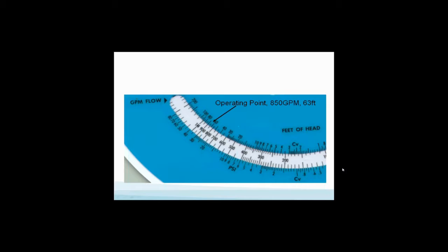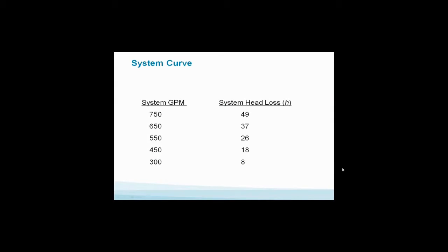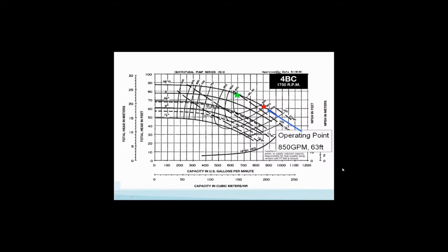And we pull these particular numbers off, any set of numbers you want to. In this case, we pull them off this way. 650 is 37, 750 is 49. This is this magical square chart right off the system sizer scale 5. What are we going to do with this? We're going to plot a system curve. And I took each one of those points, little red stars, and I plotted my system curve. That's the real curve. That's where the real world is. That's where we're really operating, 850 GPM at 63 feet of head.